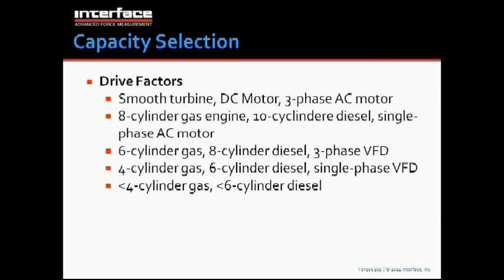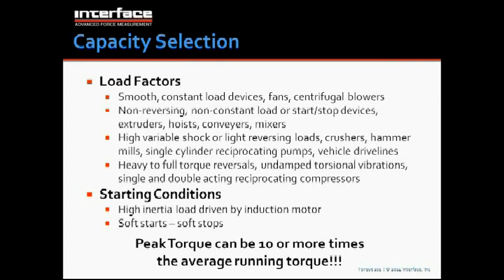Drive factors: you imagine if you're trying to spin your system using something like a smooth turbine, that's quite easy and smooth. On the other end of the spectrum, down the bottom of the list, would be, say, a 4-cylinder gas engine, where each firing of the cylinder creates a torque spike. That'll be a relatively difficult drive factor. Same thing with load. If you're spinning, say, a fan, it's quite easy to spin. Imagine on the other end of the spectrum, if you're having full torque reversals, or you're turning some kind of a grinding system like a hammer mill or something, you may have a relatively difficult load. And so you basically take the average running torque that you calculated and you multiply by load factors to come up with probable peak torque. And then you need to size the sensor using that peak torque.